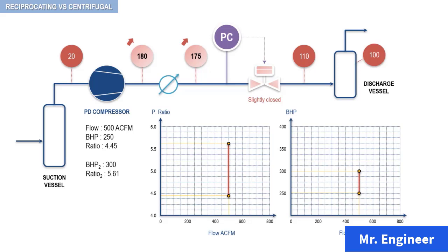Observing these plots, the characteristics of any reciprocating compressor can be defined as follows. Reciprocating compressors deliver a constant volume, have a variable head capacity, and are not self-limiting. Not self-limiting means that the pressure ratio or discharge pressure, as well as the brake horsepower, will continue to rise until the compressor case pressure is exceeded or the driver maximum horsepower is exceeded. To limit these parameters, a pressure relief valve is always required in a system incorporating any type of reciprocating compressor.